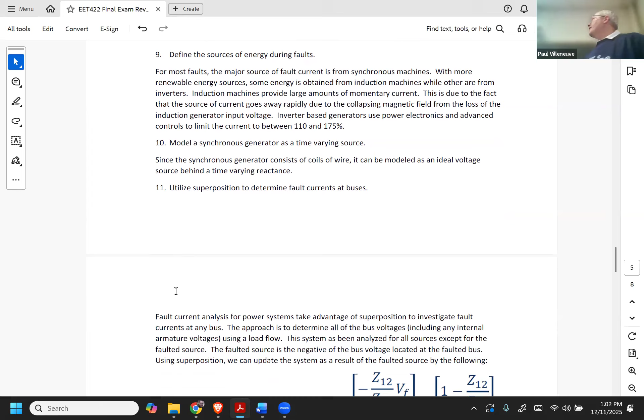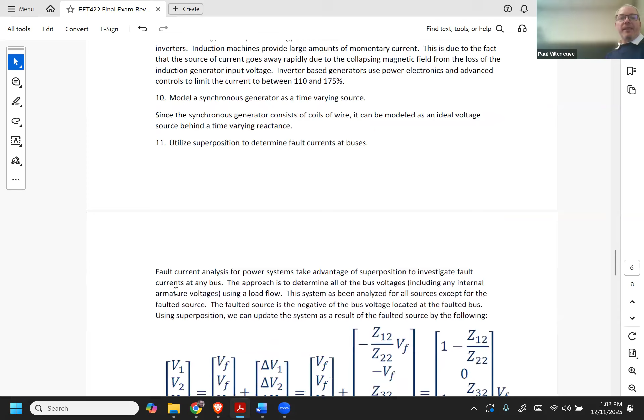So we just modeled it as an ideal source behind a time varying reactance. That's kind of the segue from number 9. Then we utilize superposition. Remember way back in the day when you were taught superposition and you're like, why would I do superposition? It seems like a lot of work when I can just get it directly. Well, we use superposition when we have a fault at a bus. We add in a fault source that is indicative of the pre-fault voltage at the fault location. And so all we're doing right here is adding in that negative voltage because we want to drag it down to 0.